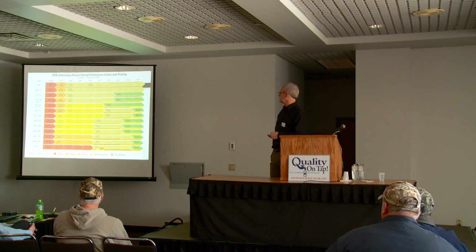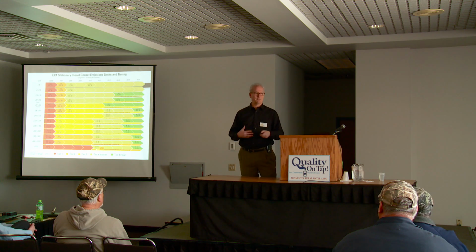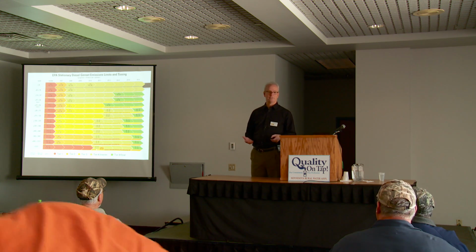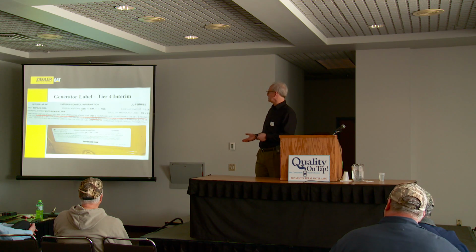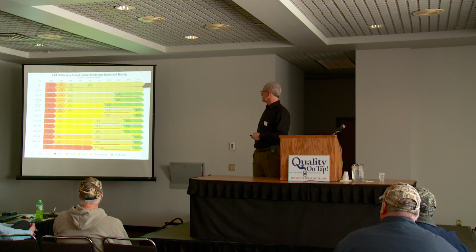So this one, again, 560 to 900. That's right in here. It was built in 2011. And it says it's certified, so it's not emergency only, it's certified, and that can be run as much as you want. It doesn't have to be run only for emergencies, it can be run on a peak shaving program, etc. So that's just, again, a couple of the examples of labels and engines.